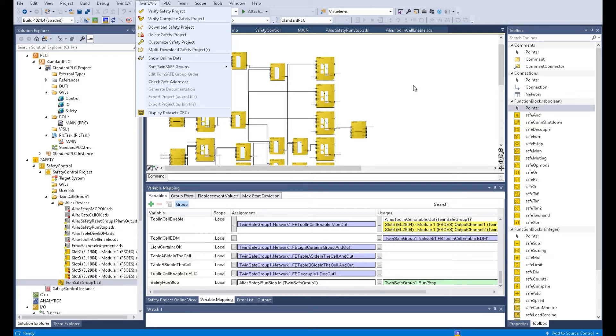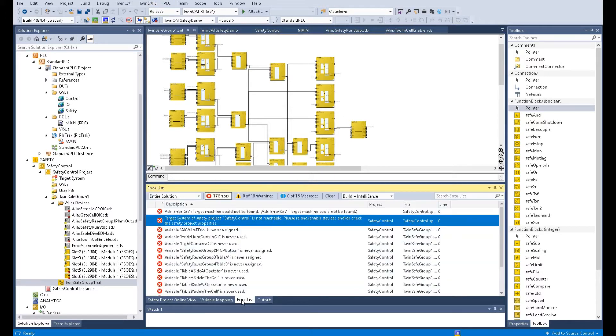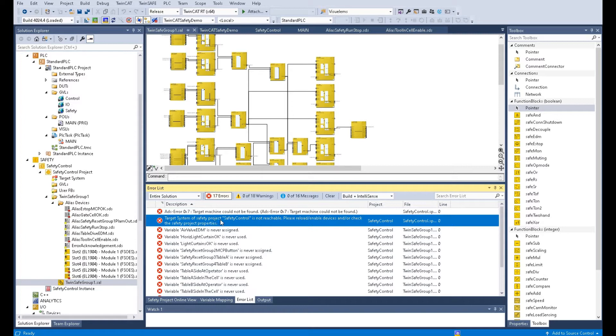In the current step, if you go to verify complete safety project, you will find the system will pop up two errors. That error means target machine cannot be found and target system of the safety project safety control is not reachable.